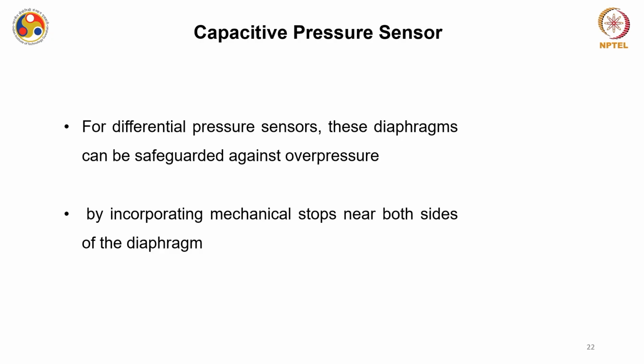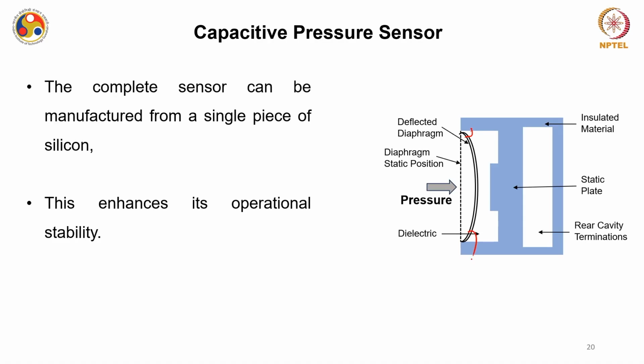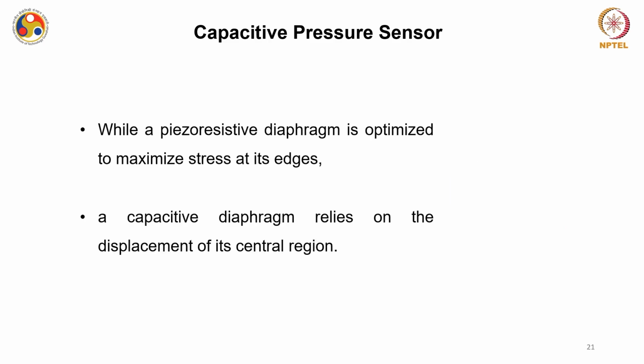Okay, so for a differential pressure sensor, these diaphragms must be safeguarded against overpressure, because you do not know which is pressure A and which is pressure B. By incorporating mechanical stops near both sides of the diaphragm, it can be achieved.